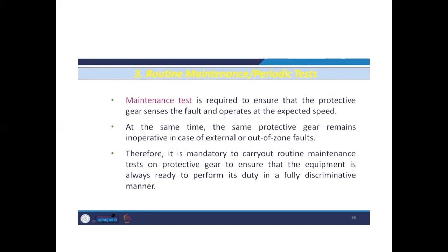So we have to check the reason behind this slow operation. At the same time, the same protective gear should remain inoperative in case of an external or out of zone fault. If it is operative, we have to check the reason. Out of zone fault means, as we have discussed with the relay, that the relay is to operate in a specific zone, because if it operates outside its zone, it will trip the whole circuit, which is undesirable. For the specific zone, the particular relay should operate so that the supply to the other equipment remains uninterrupted.